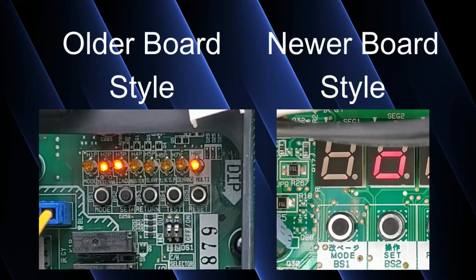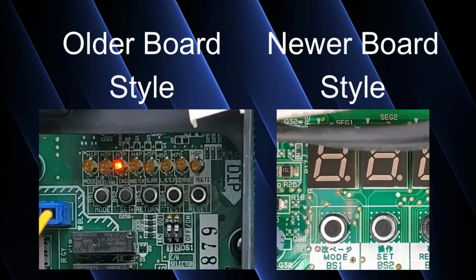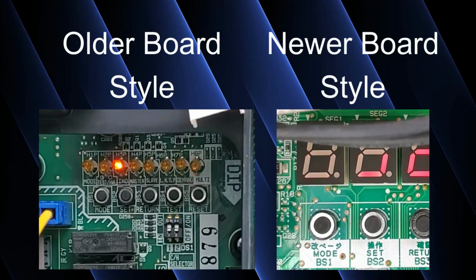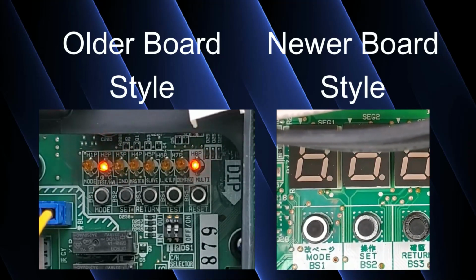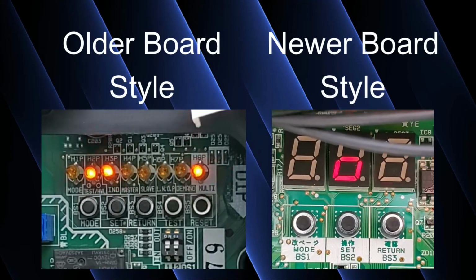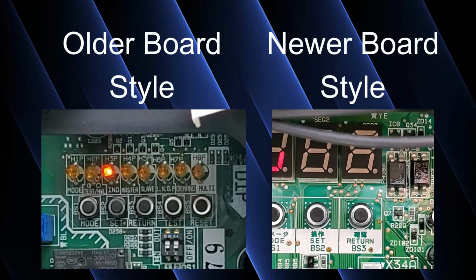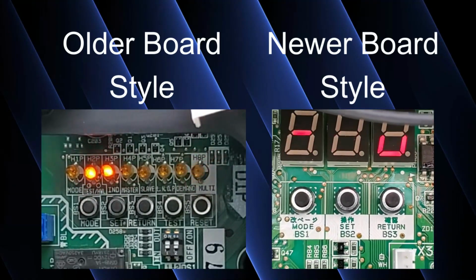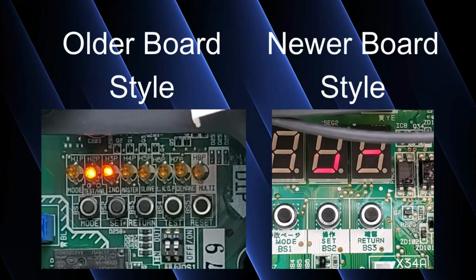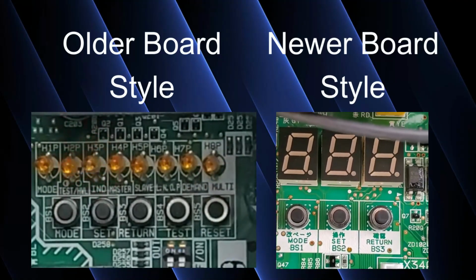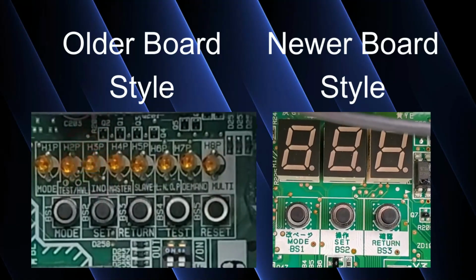You might still have one in the field, or even a SkyAir system. All those other units have the older style boards where you have all the LEDs. When you power up any of those units, H2P is going to blink, H3P is going to be on solid, and you need to sit there and wait for H3P to be the only light on. That is going to tell you, as the technician, that it has successfully completed the initialization process. It's a lot to be looking out for on the older boards, whereas with the newer boards, you just sit there and wait for a blank screen.